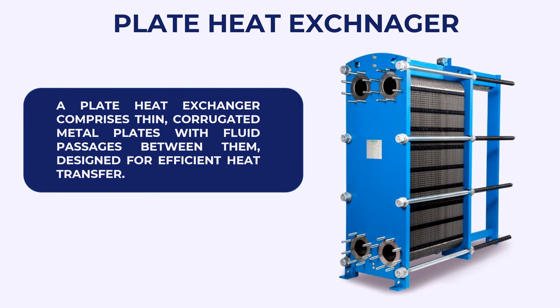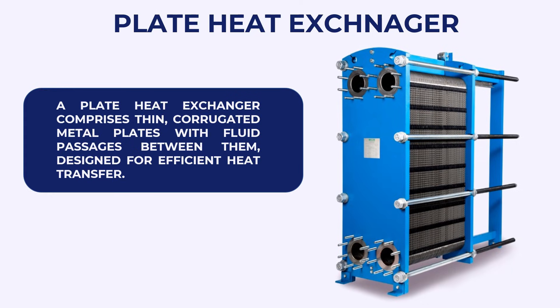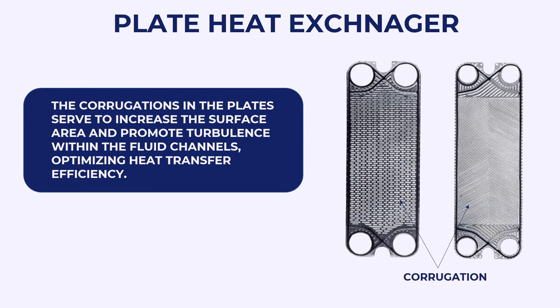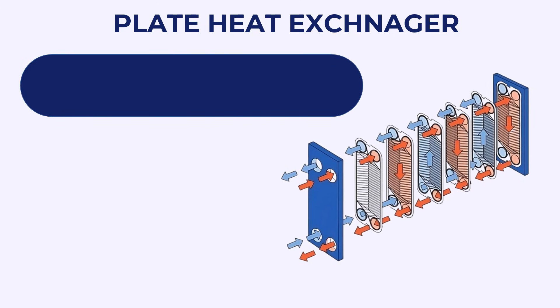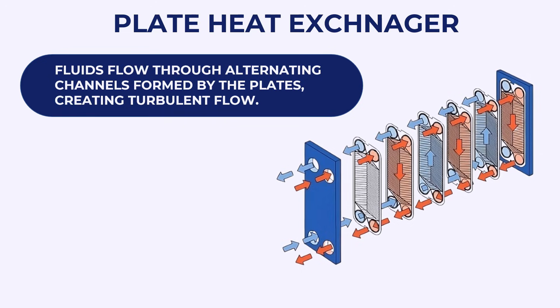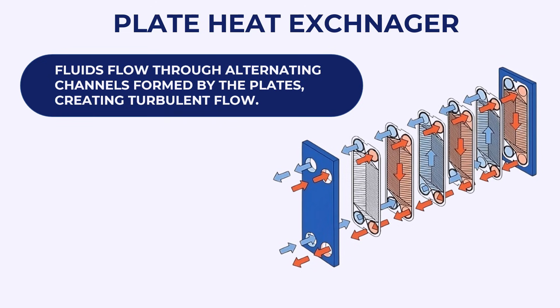Plate Heat Exchanger. A plate heat exchanger comprises thin, corrugated metal plates with fluid passages between them, designed for efficient heat transfer. The corrugations in the plates serve to increase the surface area and promote turbulence within the fluid channels, optimizing heat transfer efficiency. Fluids flow through alternating channels formed by the plates, thus creating turbulent flow.